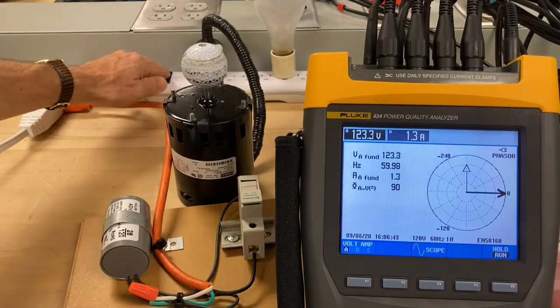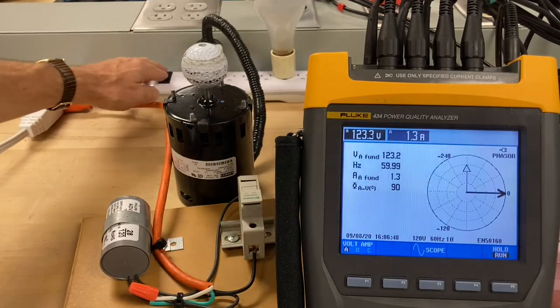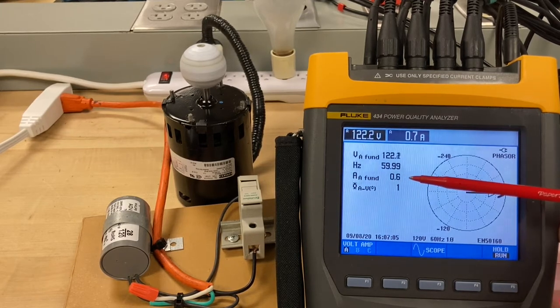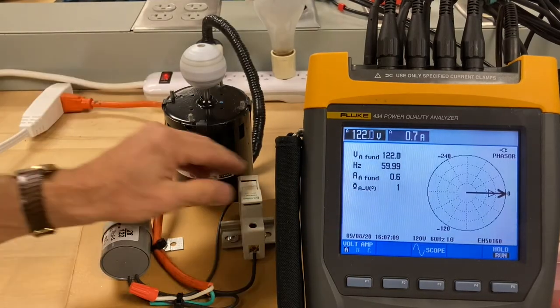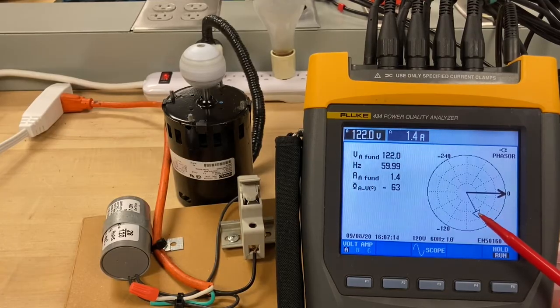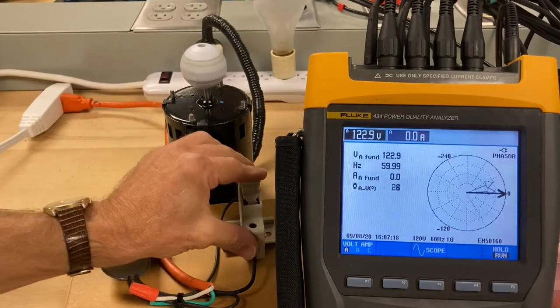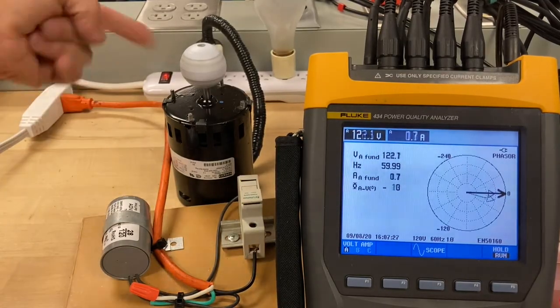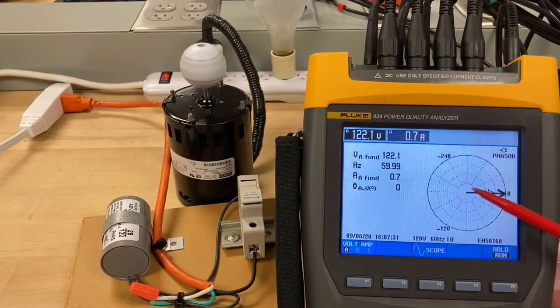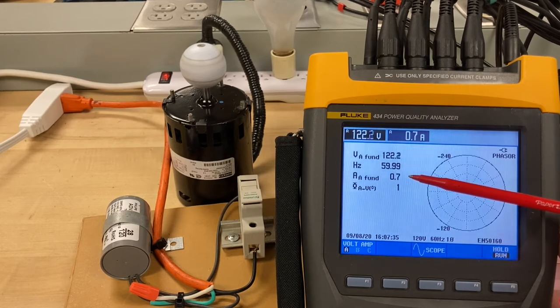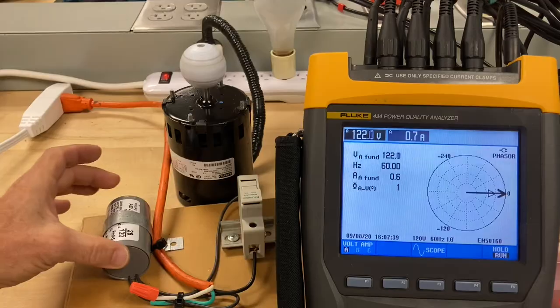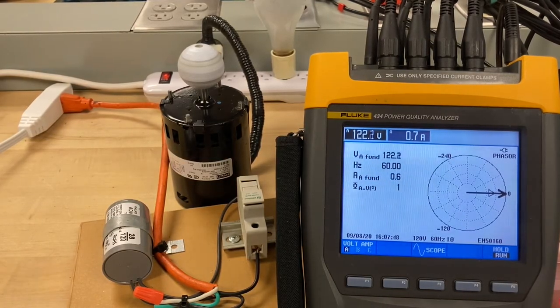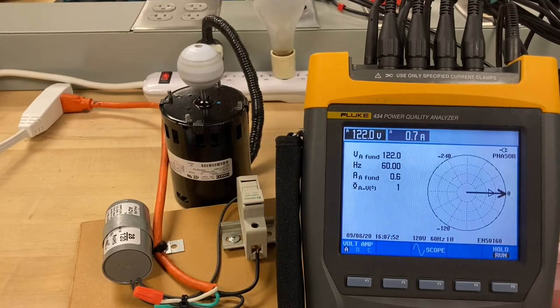So if we put the two together, the one pointing up, the other pointing at an angle down, turn them both on, and they line each other up. And the current goes down. If I just have the motor going, the current's 1.4 and out of phase. If I just have the capacitor, the current is 1.3 amps and out of phase. But when I turn them both on, it goes in phase and the current drops below what either of them is individually. So what we're seeing here is we can actually add a load and reduce the overall current.